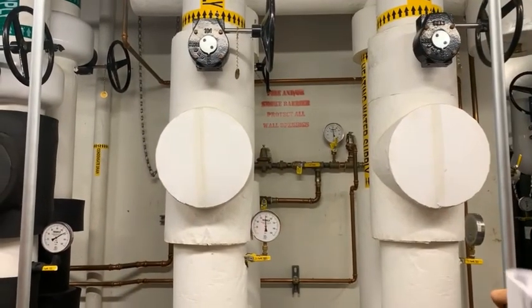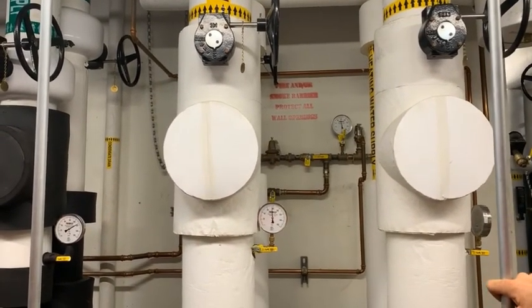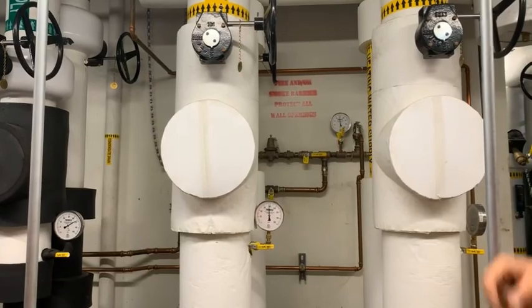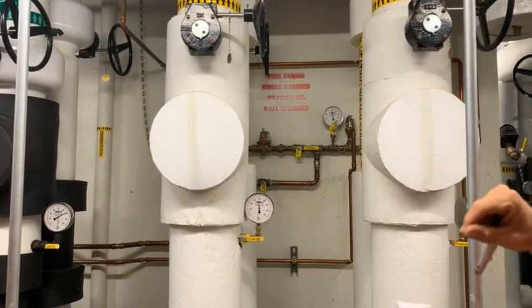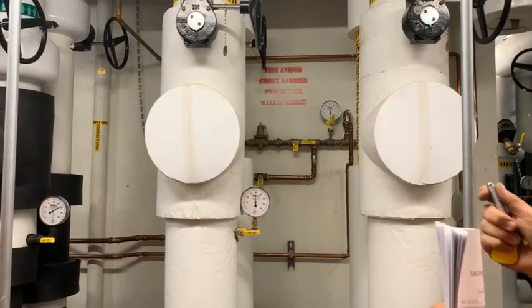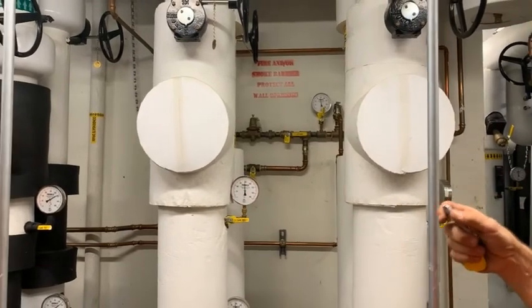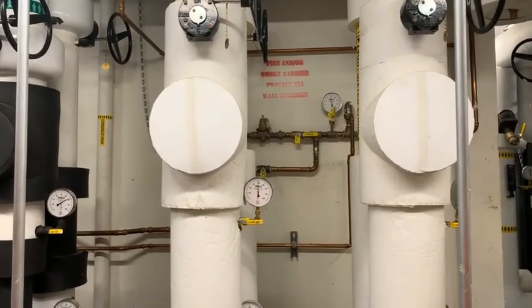That loop is a closed loop, so we shouldn't be adding water, but there could be a time where if you have to do any maintenance up on a fan coil unit, you want to make sure that when you're done, it fills the system back up instead of draining the system down from the top.